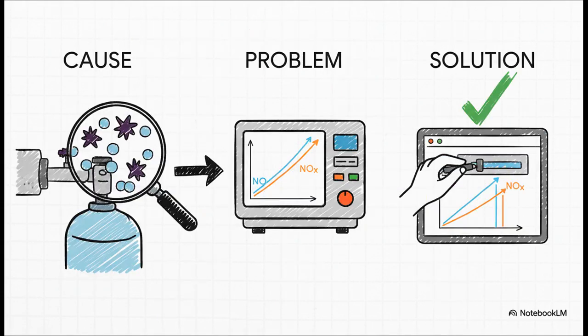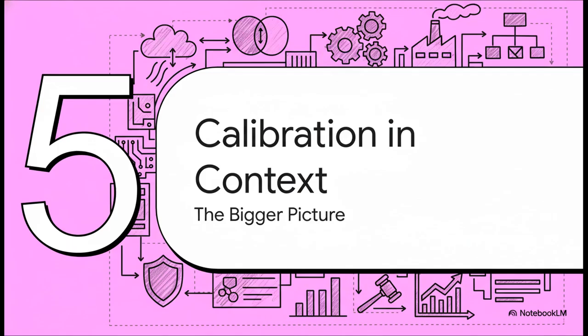And here's the twist. The problem might not even be your analyzer. It could be the gas you're using. A lot of NO span gas cylinders have tiny amounts of NO2 impurity in them. The analyzer is so sensitive it picks this up, which throws off the NOx calculation. But the fix is surprisingly easy. If you know how much impurity is in there, and you should from the gas certificate, you can just tell the analyzer to expect it during the span setup. Problem solved.